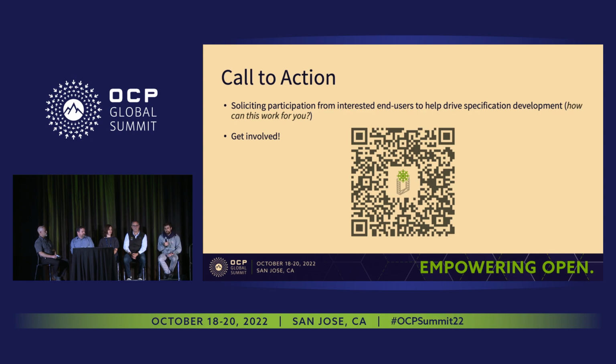So we started there 11 years ago. Then we went to a data center in a skyscraper. We have also done containerized data centers with very fabulous numbers. This morning, my colleague Leonie presented a very high density containerized data center with 2.16 megawatts IT power in a 40-foot container. And 95% of that can be captured, more or less, and this can be connected to a district heating network. So the potential of the heat reuse is not theoretical, we are doing that already.